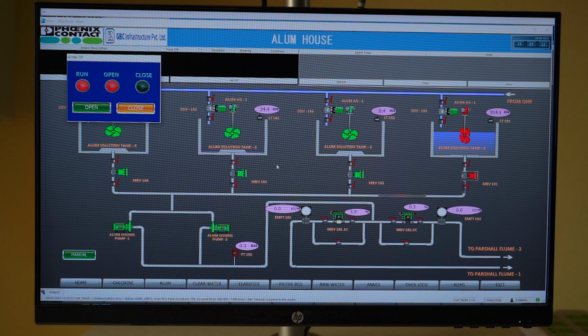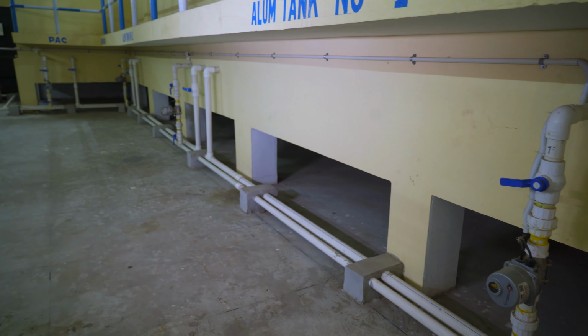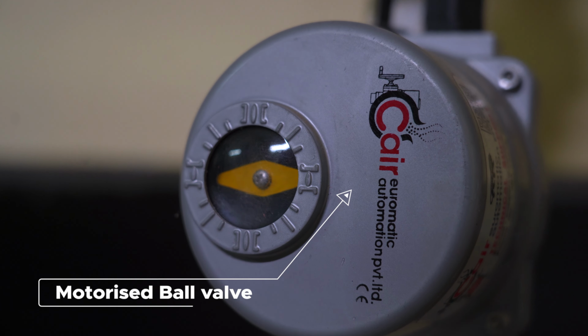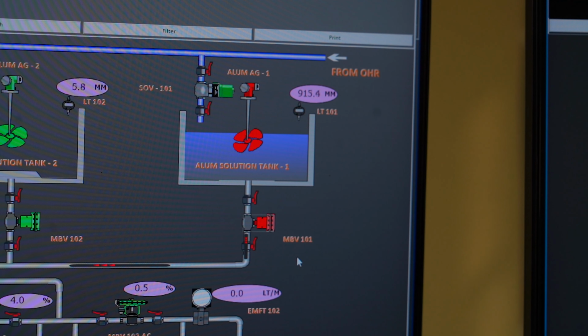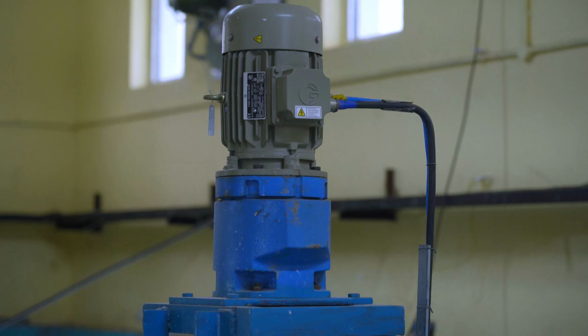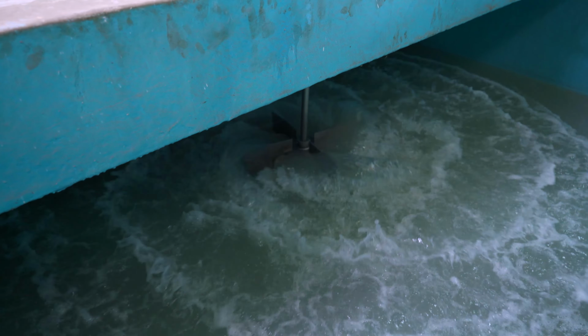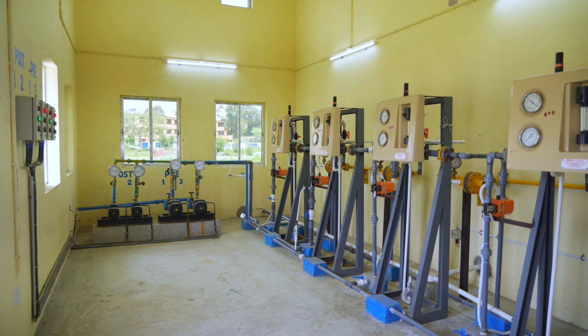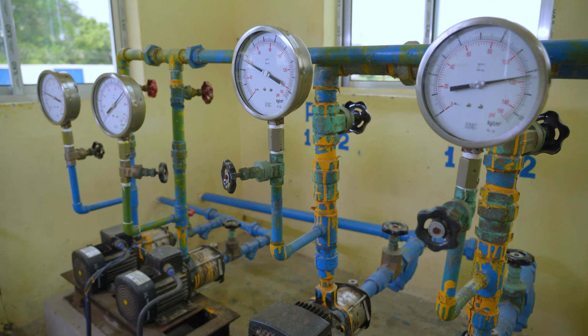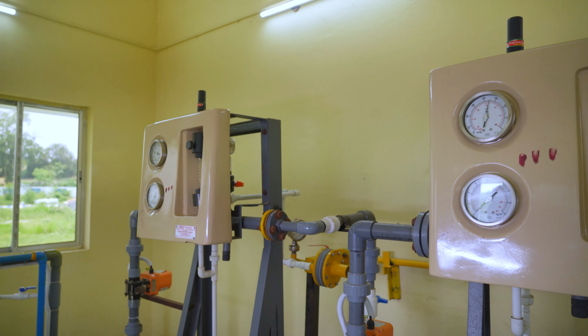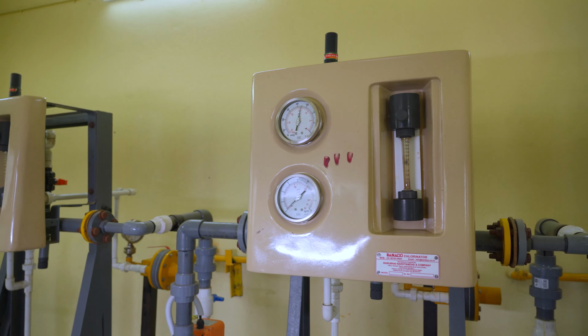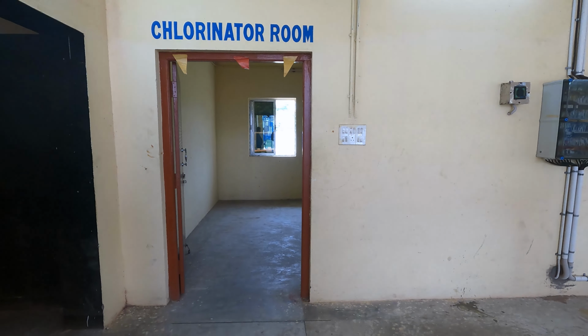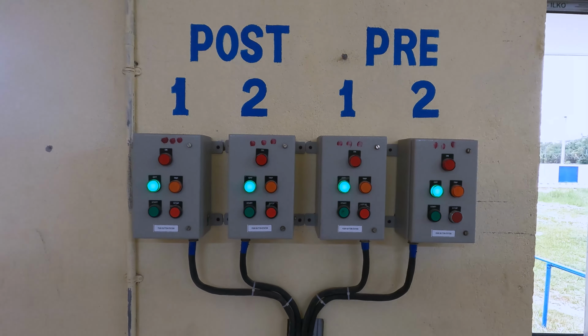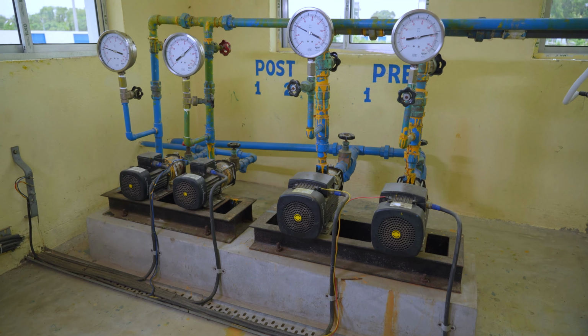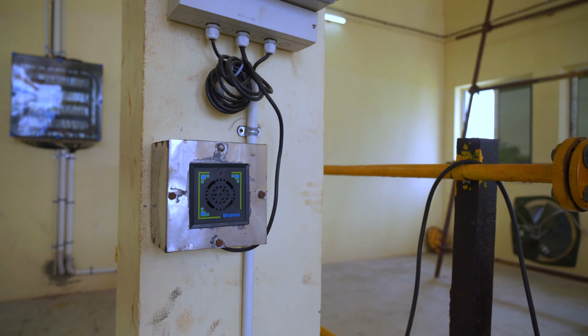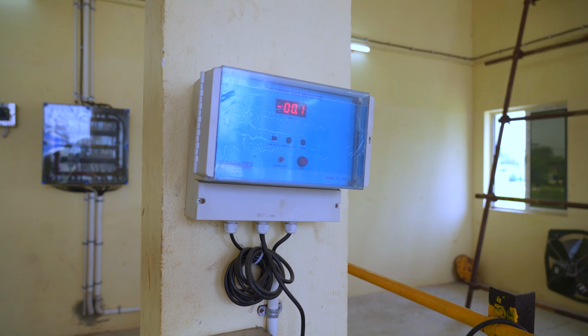Selection of alum tank is pre-decided and accordingly the motorized ball valve fitted on the delivery line of the respective tank is being opened automatically. The alum agitator starts first for the continuous stirring, followed by booster pumps of both pre-chlorine and post-chlorine starts. The pre-chlorination and post-chlorination dosing system are set up at the chlorinator room inside the chemical house, where booster pumps, pre- and post-chlorination dosing system with adequate precaution like gas sensors are present.